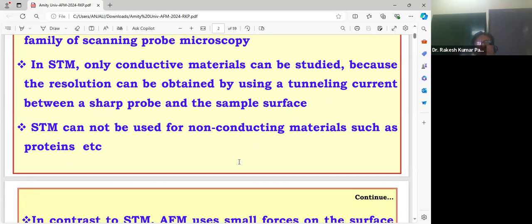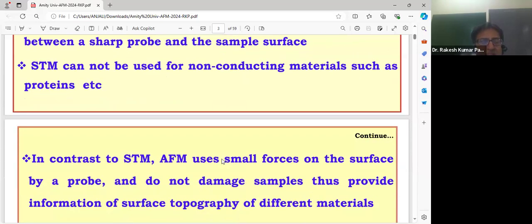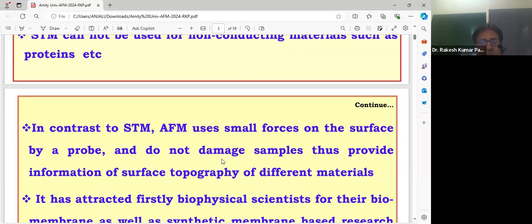Now here there are many samples. We are having biological samples, and as you know, most of the biological samples are non-conducting samples. So we cannot use STM for non-conducting samples, such as proteins, biological tissues, cells, etc. Whereas in case of AFM, AFM uses small forces on the surface by a probe, that is AFM probe, and it is called tip. And it does not damage the samples.